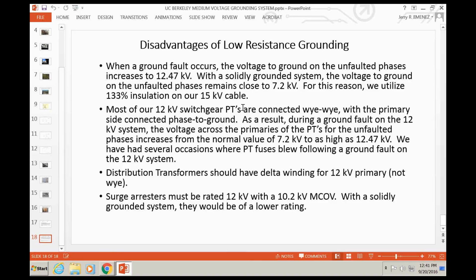Did you say that during that $20 million renovation back in '88, '89 you replaced most of your medium voltage cabling? Those are two separate instances. In '89 to '90 to '91, that's when we changed from 4160 distribution to 12 kV. That's when the medium voltage cable was replaced. And then in 1999 to 2000 is when we redid the substations to give us all those transformers, and that's when we implemented this low resistance grounding scheme on the transformers.